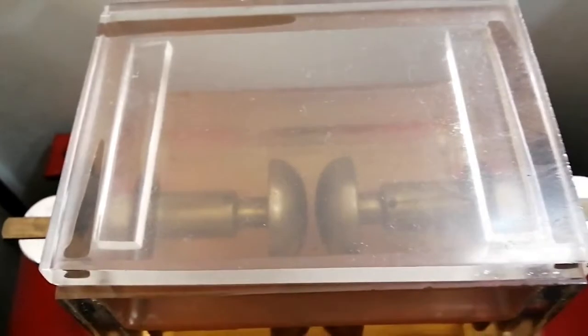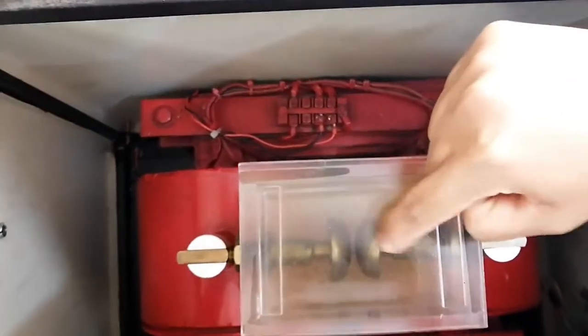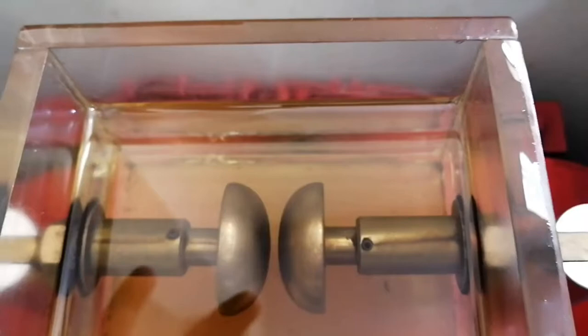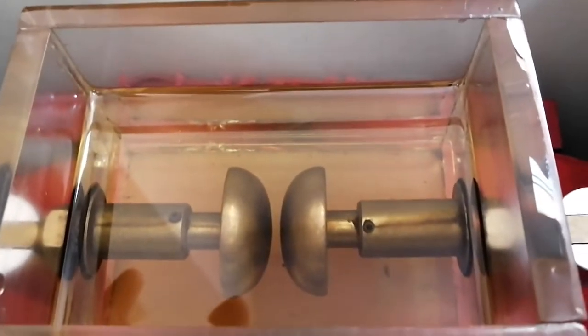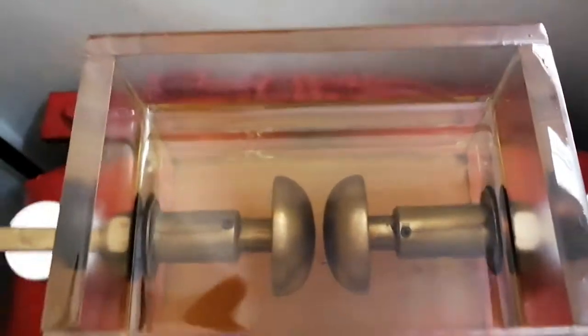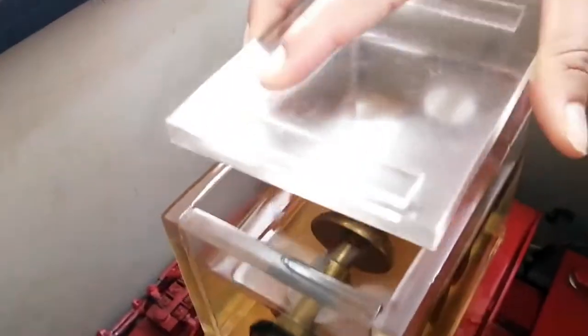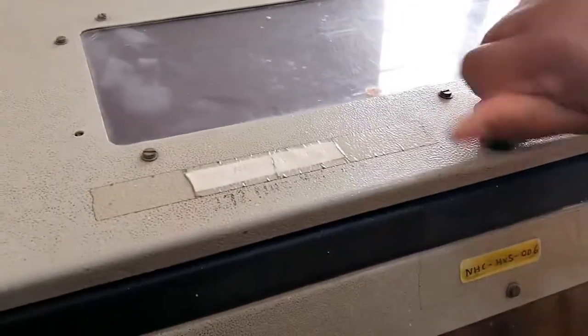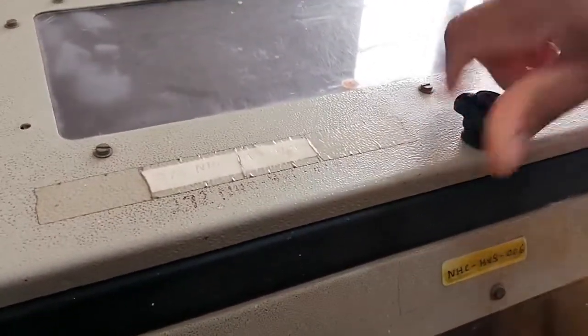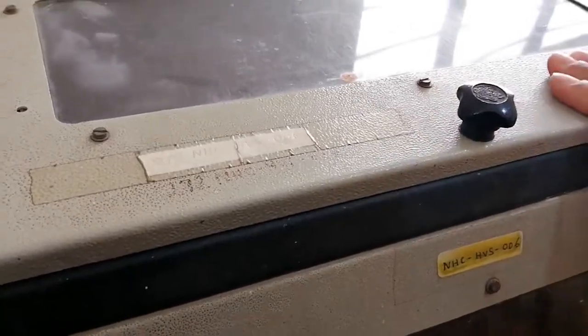This is the transformer oil tank, and inside you can see the transformer oil and the sphere rods. The gap between the sphere rods is already maintained and preset, so there is no need to set it. The only thing we have to confirm is whether the transformer oil tank is closed properly. The entire kit should be closed rigidly, and you have to fix this cap so that nobody opens the setup in between the experiment.